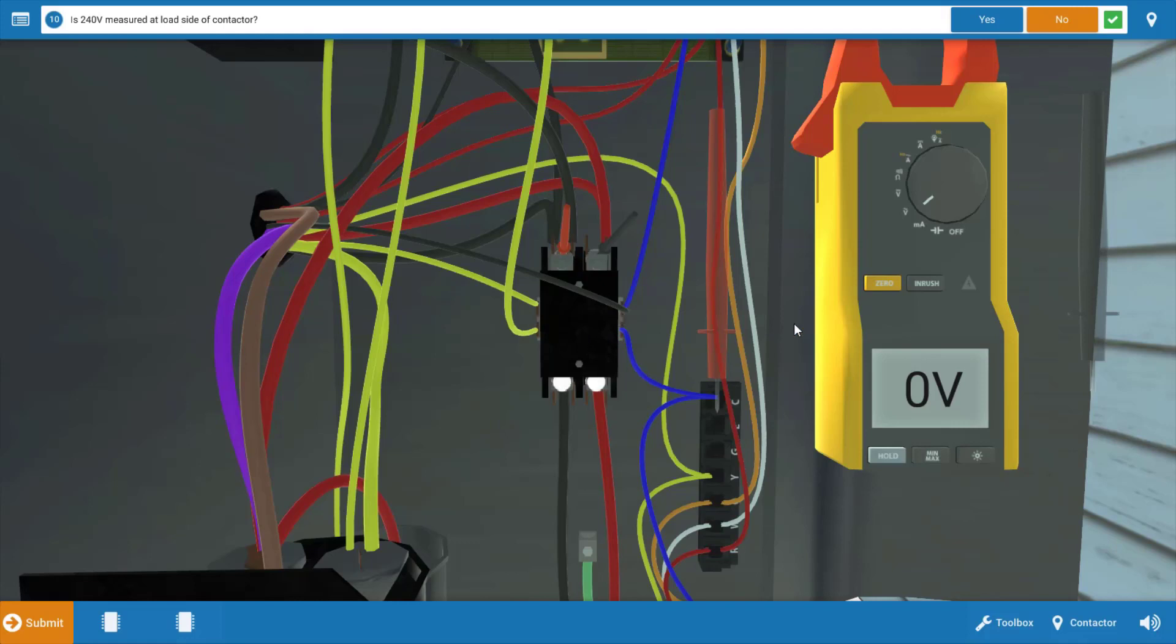Now, could we have a problem with the contacts? Well, sure, but more than likely the coil is open. And because this is a residential unit, and the contactor is a replaceable component, it's not repairable, it's not really going to be necessary to do a resistance check of the coil. We know the contactor's at fault. Again, with 24 volts to the coil, it should be energized, and it should be pulling those contacts in.